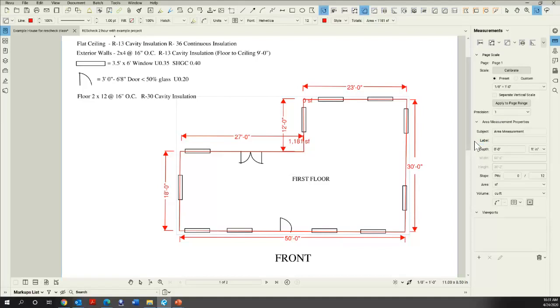And we're going to take the windows. No, you don't. Excellent point. If I didn't say that before, the software does that. That's why it's important. You're always doing gross area, always. Do not subtract the windows. The software does it. That's why it's important to make sure that the windows and the walls are connected correctly. So you always do gross area.